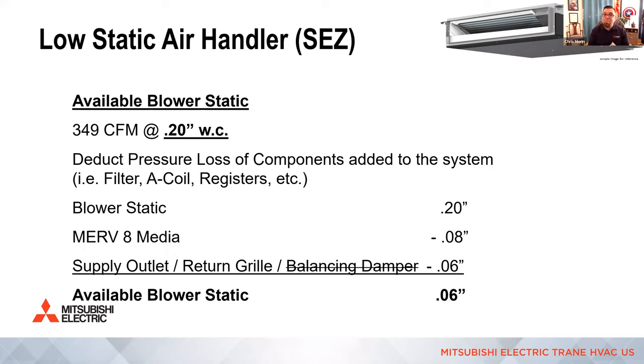Now, when you do this math, you need to have at least 0.06 available or above to make this system work, just on the top portion of the friction rate math, right? So just on this step 1 through 3 on your friction rate worksheet. If you don't have at least 0.06, then you need to either increase your available static pressure, so go from 0.14 to 0.2, or reduce how many components you're adding to the system, all right? Otherwise, you won't have enough static pressure to overcome that when things start to get dirty.